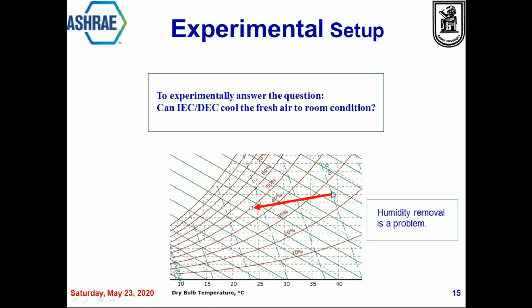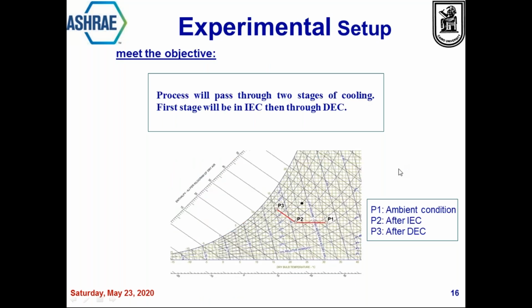For example, you start at 40 degrees centigrade and relative humidity about 30%, then you go down to 50% relative humidity, but temperature about 23 or 24 degrees centigrade. So we can do both of these in consecutive processes. First, we take the ambient air and cool it down by indirect evaporative cooling from stage 1 to stage 2. Then we do direct evaporative cooling from stage 2 to stage 3. Now we have cooled air, but at high relative humidity. Then we can cool down with mechanical refrigeration, but at a lower enthalpy drop than if we use the conventional method.